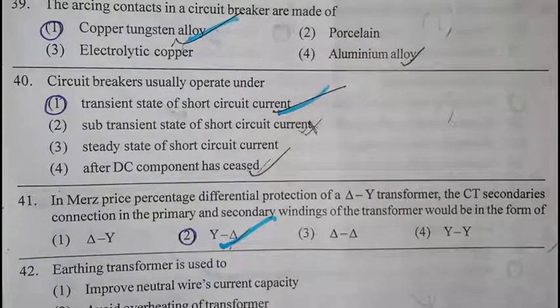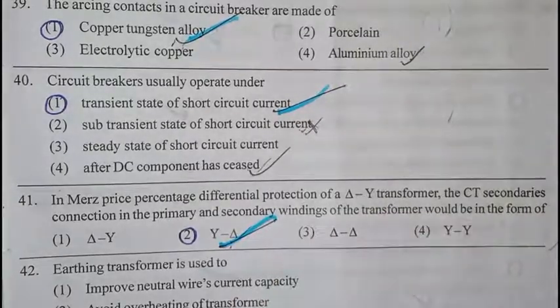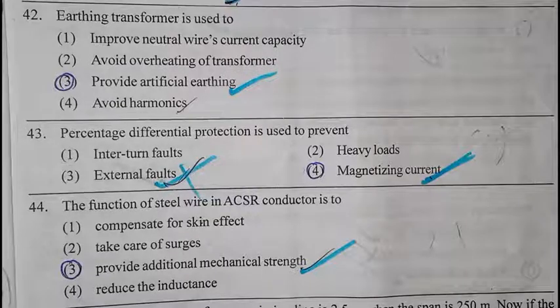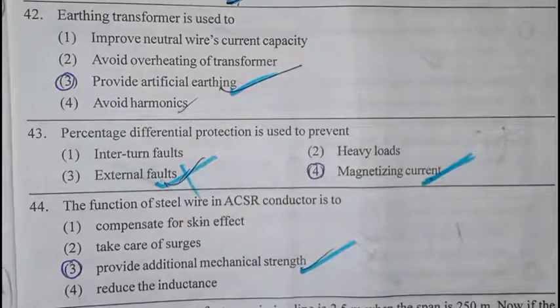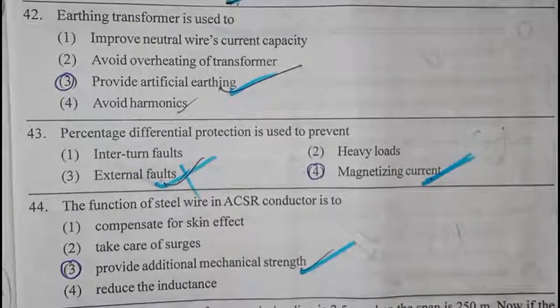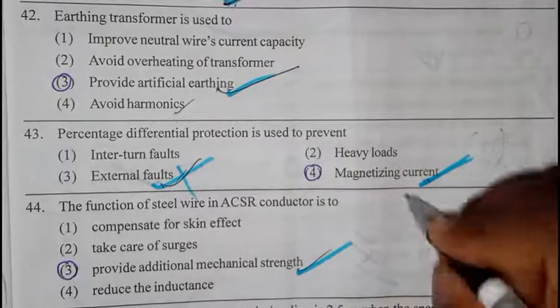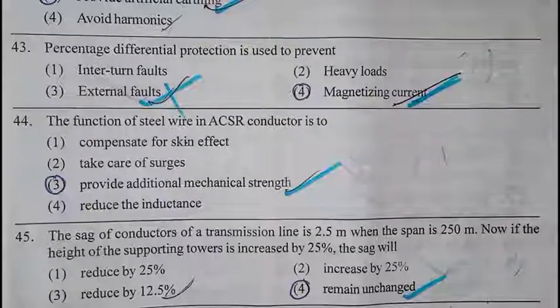Question number 41. In Merz-Price percentage differential protection of a delta-star transformer, the CT secondaries connection in the primary and secondary windings of the transformer would be in the form of star-delta. Question number 42. Earthing transformer is used to provide artificial earthing. Question number 43. Percentage differential protection is used to prevent magnetizing current.